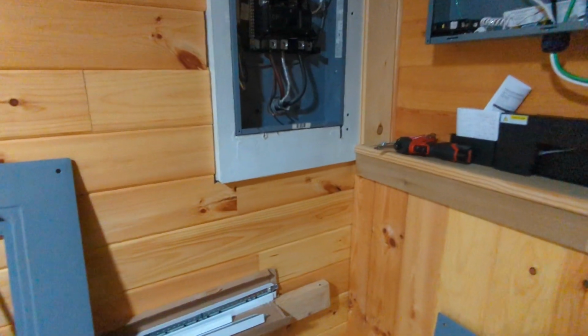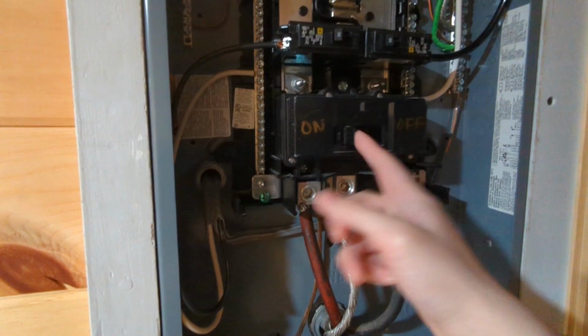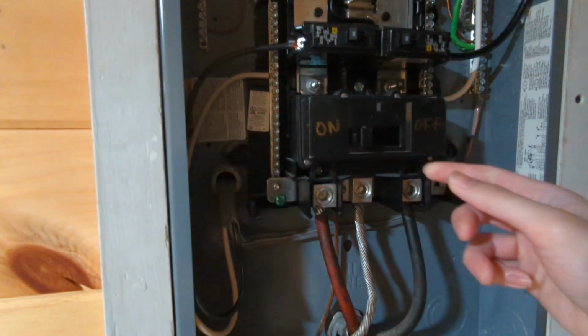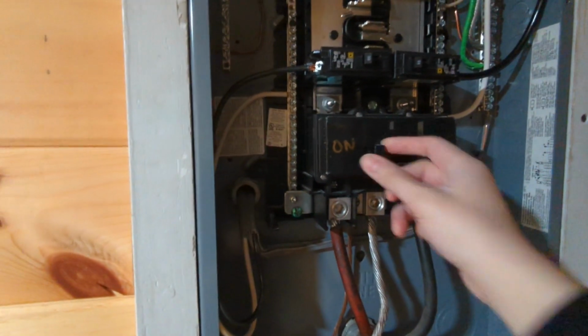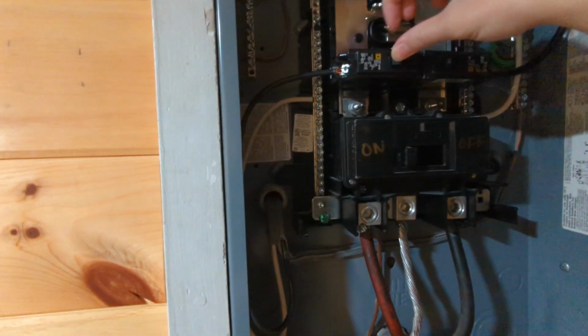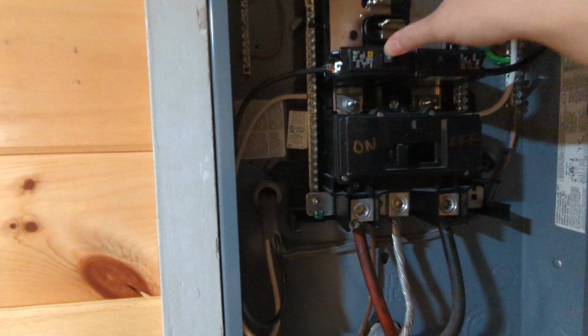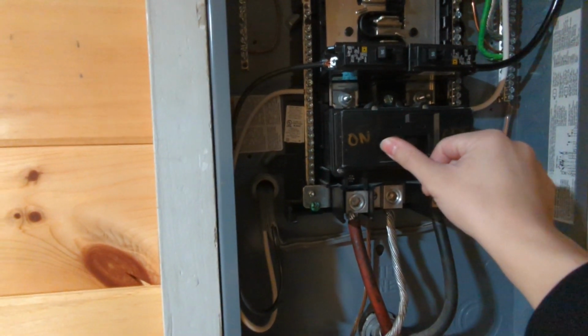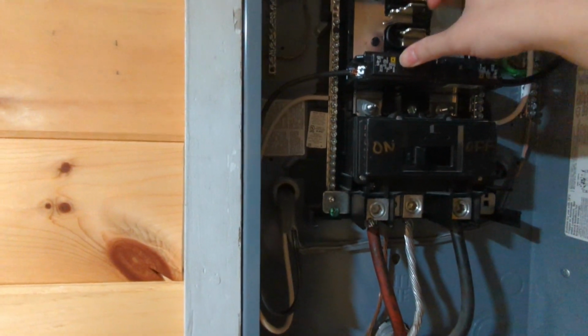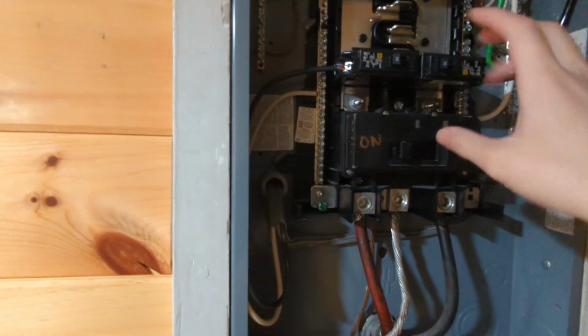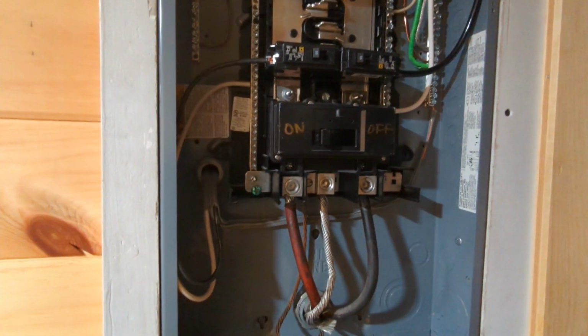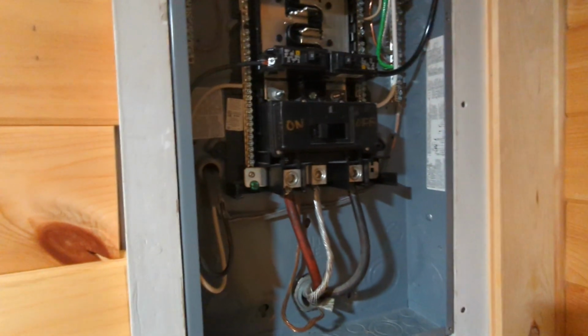set up. I hooked up a generator lockout switch where if your primary switch from your service wires coming in, if it's on, your generator circuit breaker has to be off. If your primary big breaker is off, then you can turn on your generator charging circuit, right? So the 2 switches here, only one of them can be on at the same time. So it never allows both, and that's what the lockout plate does.